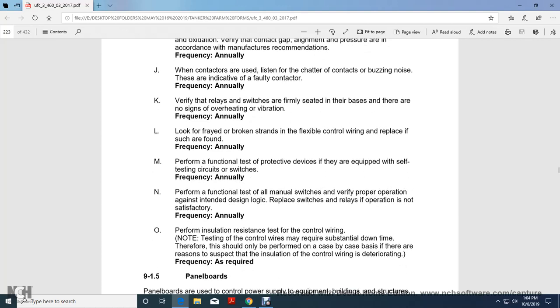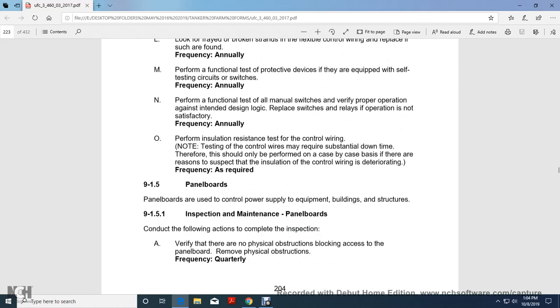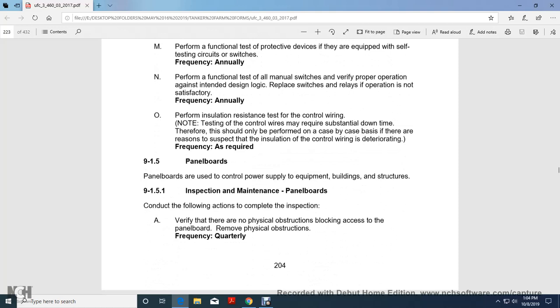Perform functional tests of all the manual switches. Verify proper operation against the intended design logic. Replace the switches if the operation is not satisfactory. Perform insulation resistance testing of the control wiring. Note that testing the control wires may require substantial downtime, therefore it should only be performed on a case-by-case basis, if there is reason to suspect the insulation of the control wiring is deteriorating and that testing is required.